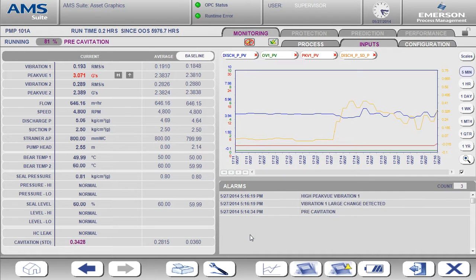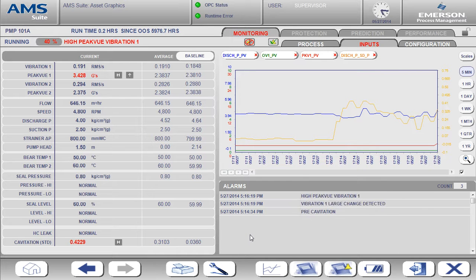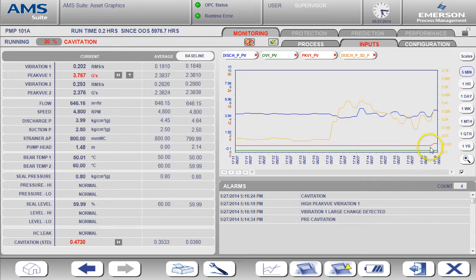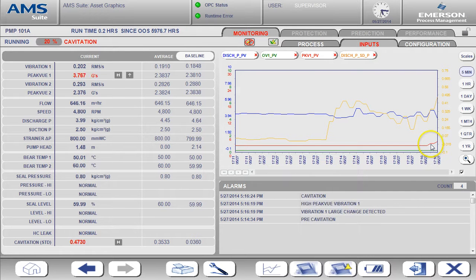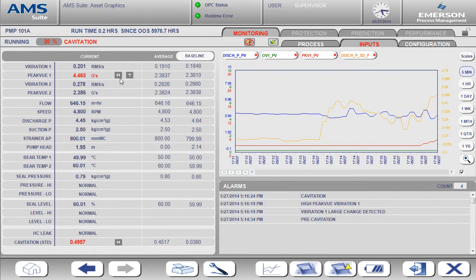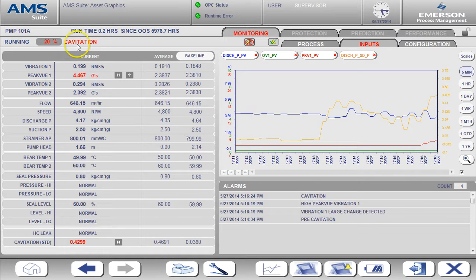Let's now look at the conditions that cause the cavitation alert to be active. Keep an eye on the vibration measurements on the trend. You'll see that the PeakVue value is increasing and is now high. Now look at the health value and alarm. We are now showing 20% health and a critical alert for cavitation.